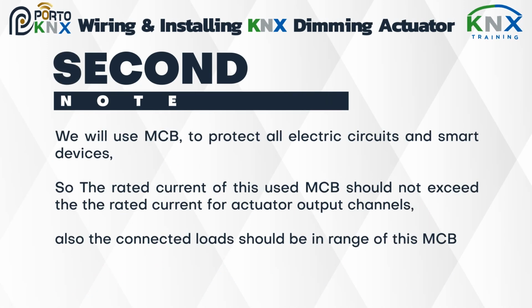Second note, we will use an MCB to protect all electric circuits and smart devices, so the rated current of the MCB used should not exceed the rated current of the actuator output channels. Also, the connected loads should be within the range of this MCB.